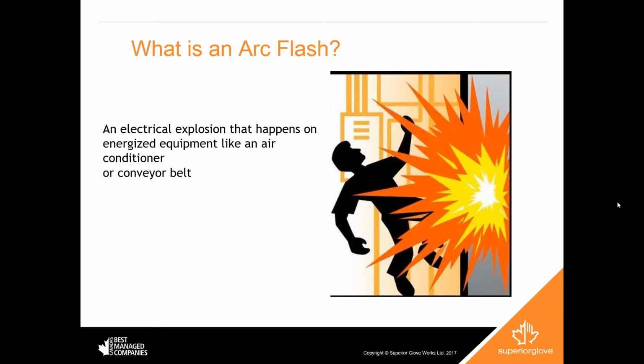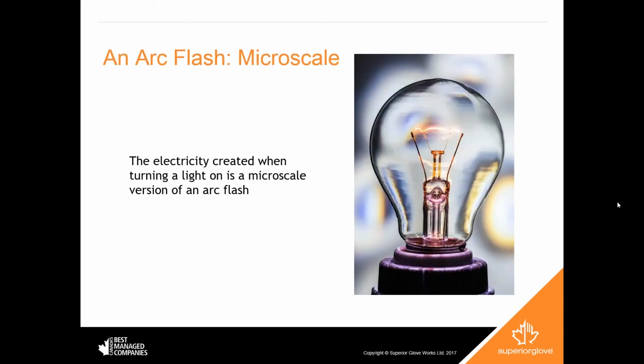I'll pass this over to you now, Robert. Thank you, Matt. Most people don't think about it, but a good everyday example of an arc flash is flipping the switch in your house and turning on a light bulb. The heating of the element creates a very minor, mild arc flash in that process. An arc flash in the industrial world can reach temperatures of over 35,000 degrees Fahrenheit, which is over 4 times the heat of the sun. And depending on the voltage of the machines and where the workers are, there are still dangers of up to 2nd-degree burns as far as 20 to 30 feet away from the machinery you might be working on.